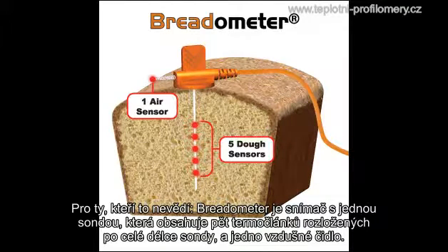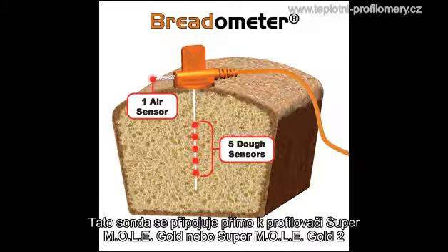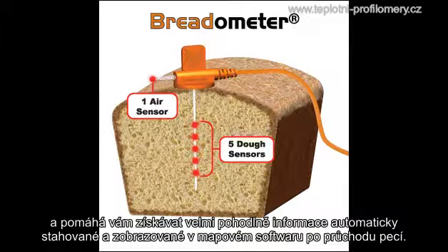For those who don't know, the Breadometer probe is a single probe sensor which has five thermocouples embedded along the length of the probe, plus one air sensor. This probe plugs in directly to a Supermole Gold or Supermole Gold 2 profiler to help you get convenient information automatically downloaded and displayed in MAP software after an oven run.